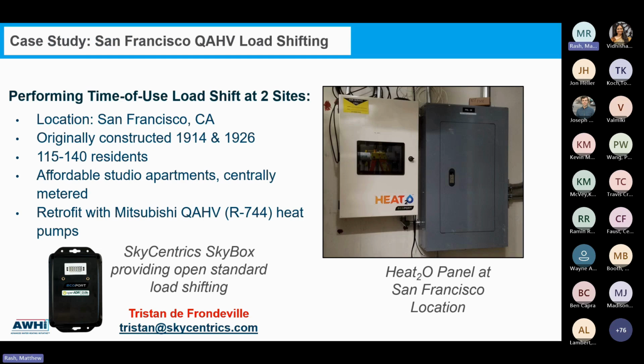Again, there's a supervisory panel option in addition to that tank temperature control panel on the kit and the Connect. That's what brings in this capability for demand response and COP monitoring. That's where you'll get your CTA 2045, and a much more expansive BACnet IP points list. And by the way, all this literature is published today on our Mitsubishi Pro website. You can go there and look at these submittals. If you just type in QAHV Connect or QAHV Kit into Mitsubishi Pro, you'll get detailed submittals.